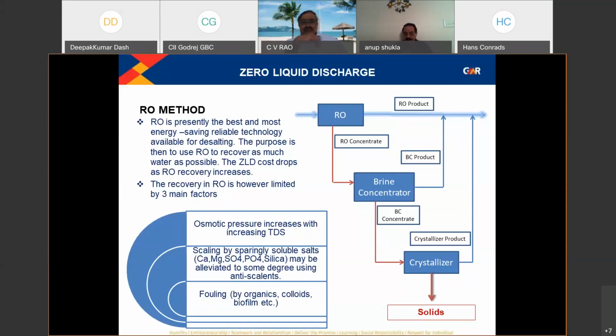In the first stage, it can be because of chemicals getting carried forward; mainly we find the coagulants used in the pre-treatment section. If it is found in the last stage, then the probability is scaling or ineffectiveness of the antiscalants used. In scaling, calcium, magnesium and sulfates are taken care of by the antiscalants present in the market, but for silica there is a limitation.